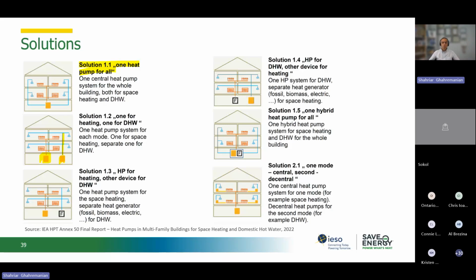This solution might be better because now we have a separate heat pump. Sometimes we don't need the space heating, but the domestic hot water needs to run, and then Legionella can grow in those situations. Based on ASHRAE standard, the temperature should be above 57 to 60 degrees Celsius to prevent Legionella from growing inside the warm water. Legionella is a very strong bacteria and can survive at that hot temperature.